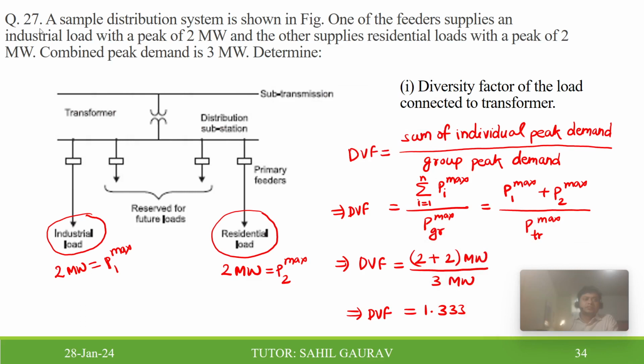Here in this problem, a sample distribution system is shown in the figure. One of the feeders supplies an industrial load with a peak of 2 megawatt. Another supplies a residential load with a peak of 2 megawatt. So one is an industrial load having a peak demand of 2 megawatt, and a residential load having a peak demand of 2 megawatt. Combined peak demand is 3 megawatt. You have to determine the diversity factor.